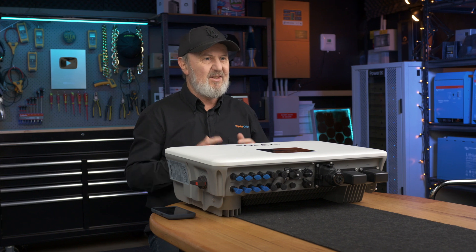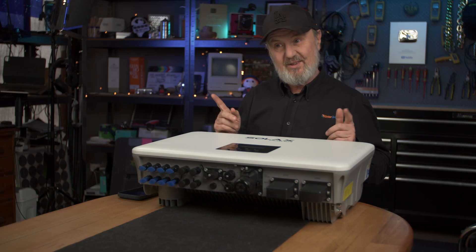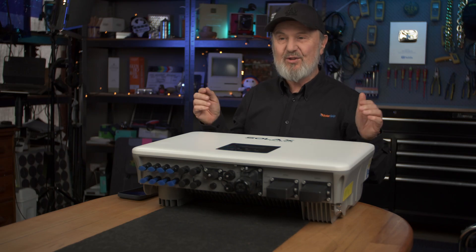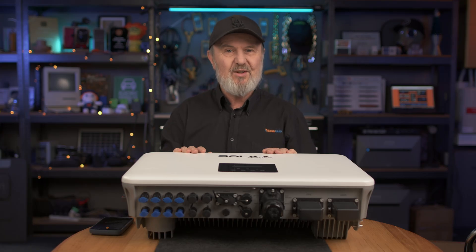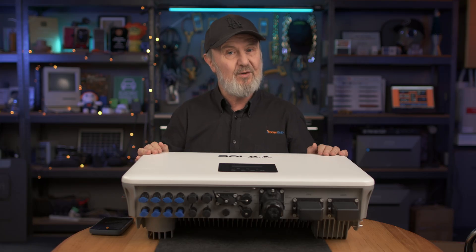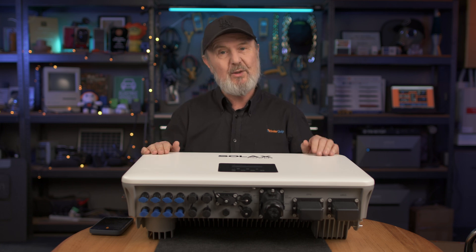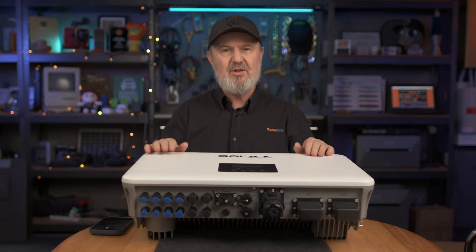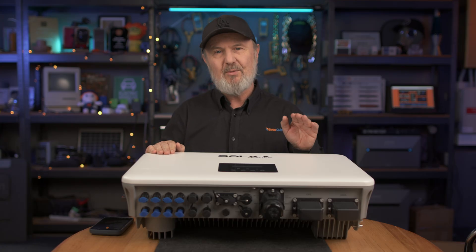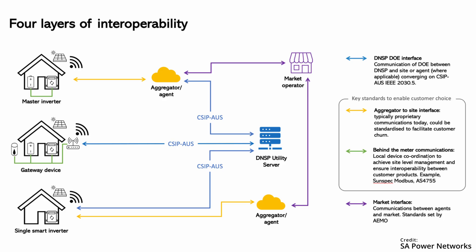CSIP AUS is the technical standard that means the DNSP — the distribution network service provider — can control the output of your inverter within 10 milliseconds. Mostly it's about ramping it down. The benefit to you as an end user is they'll let you put a really big inverter on. This is a 10 kilowatt inverter — you can put 20 kilowatts of solar on it with a 200% oversizing ratio for PV. With CSIP AUS, utilities can limit you dynamically, so if there's too much renewables entering the grid on a sunny day, they can just ramp you down a bit, but most of the time you benefit from having a bigger system.